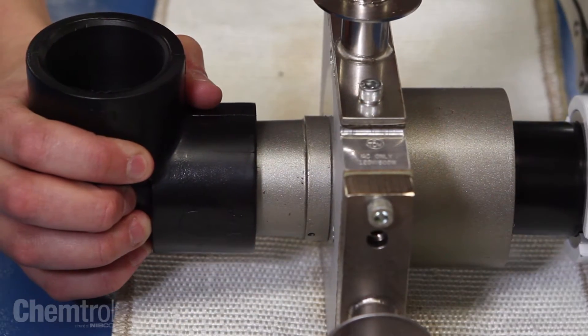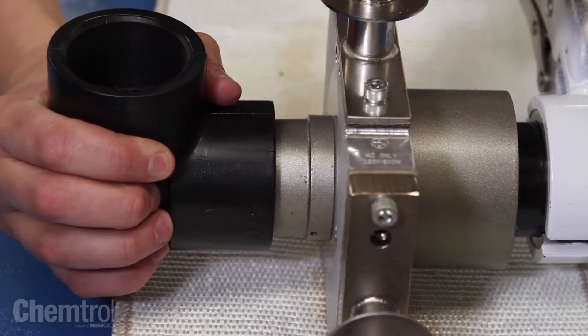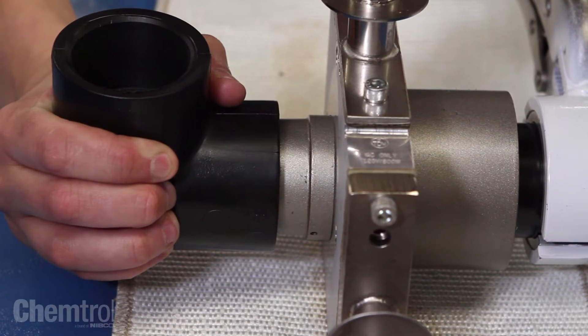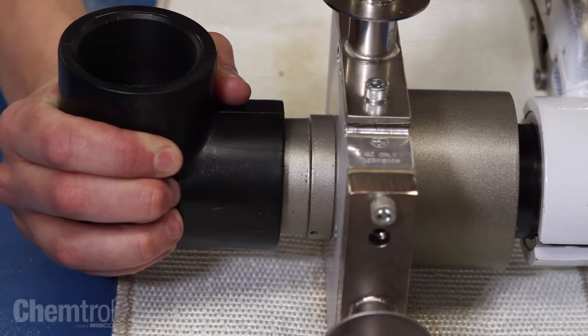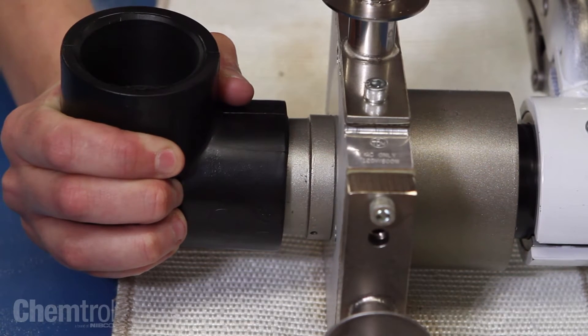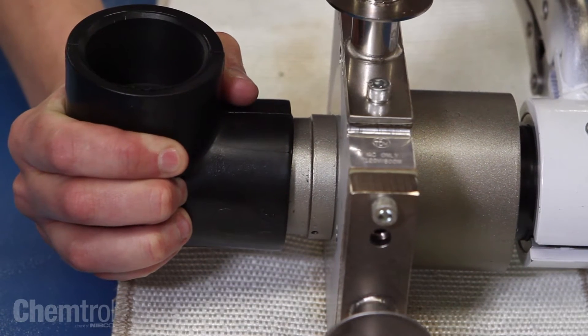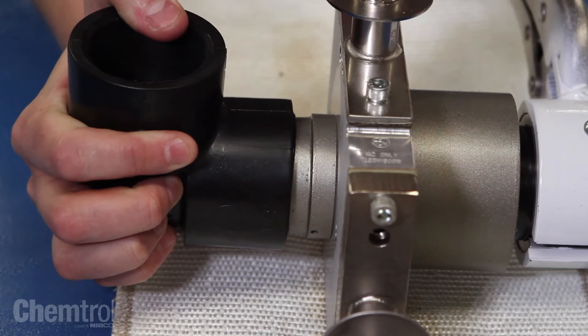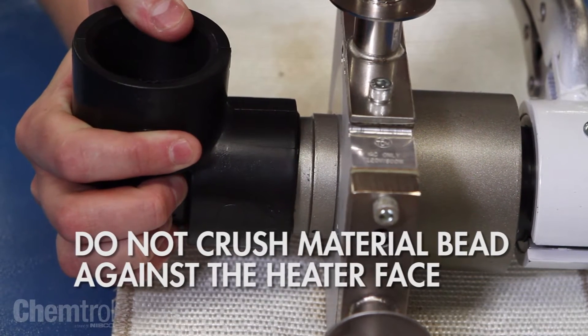Simultaneously and uniformly insert the pipe and fitting onto the heater faces. Do not force, wiggle, or twist the fitting onto the heater face. It should melt on by applying consistent pressure. Be sure not to crush the material bead against the heater face.